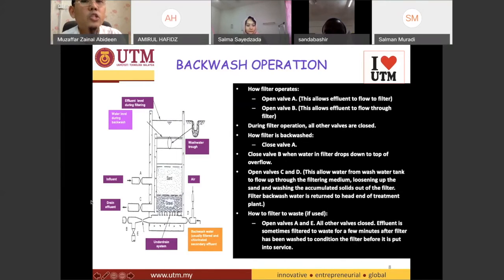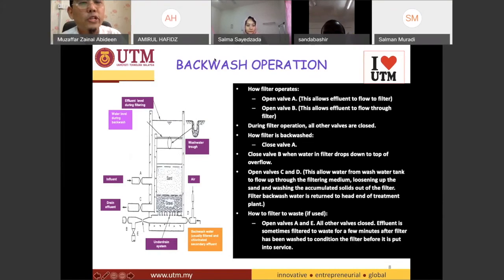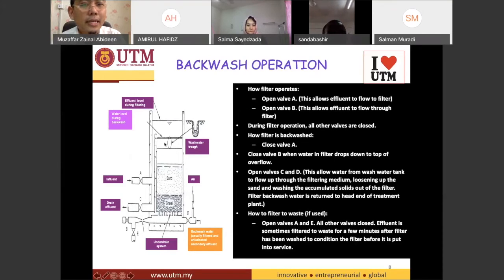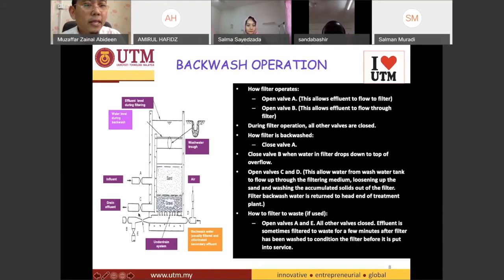The reverse flow removes all the clogging materials and waste, and it goes out through valve C. We call this cleaning process the backwash operation. Once the filter is clean, we close valve D, valve C, and valve B, and open up valve A and E.